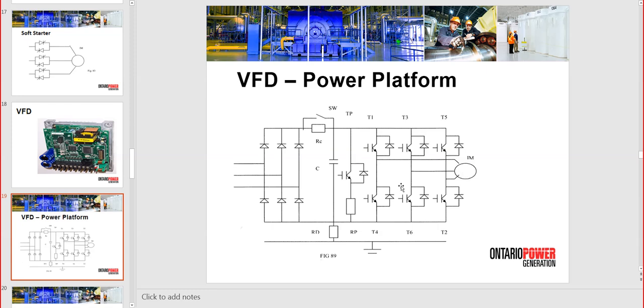So you have a parameter to set up the DC injection braking, like how long you want this to take place and what is the percentage, from 50% to 100% of full current. So DC will be applied to the motor as opposed to AC when you do DC injection braking, and you can hear a noise clearly in the motor. So yes, we can do dynamic braking, DC injection braking, and plugging.